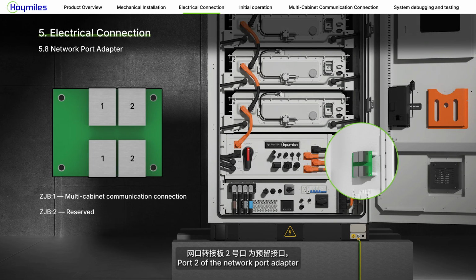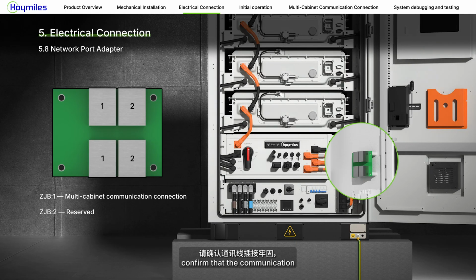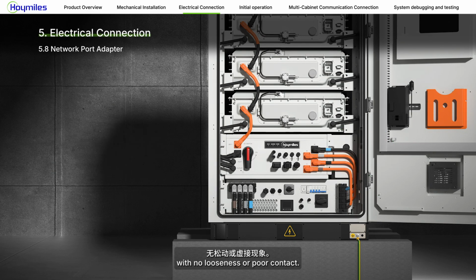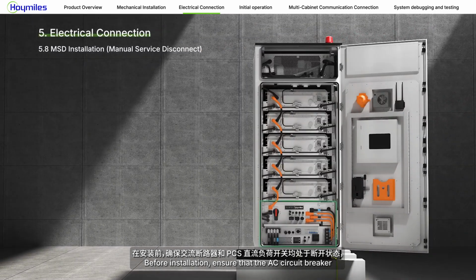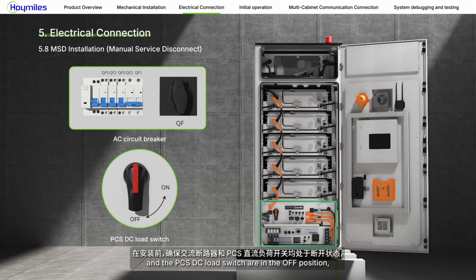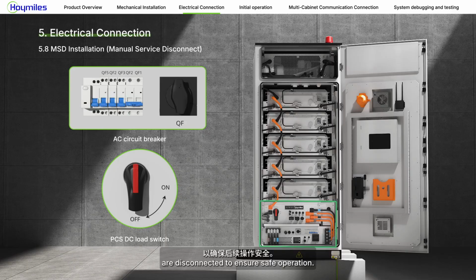Port 2 of the network port adapter is a reserved interface and is not used at present. After the connection is completed, confirm that the communication cables are securely plugged in, with no looseness or poor contact. Before installation, ensure that the AC circuit breaker and the PCS DC load switch are in the off position, and confirm that all upstream and downstream grid-side circuit breakers of the energy storage system are disconnected to ensure safe operation.